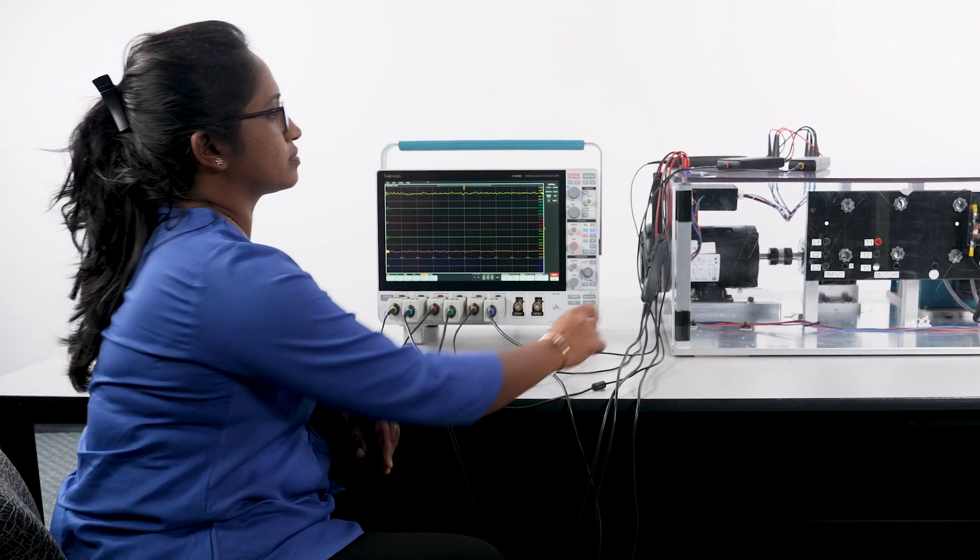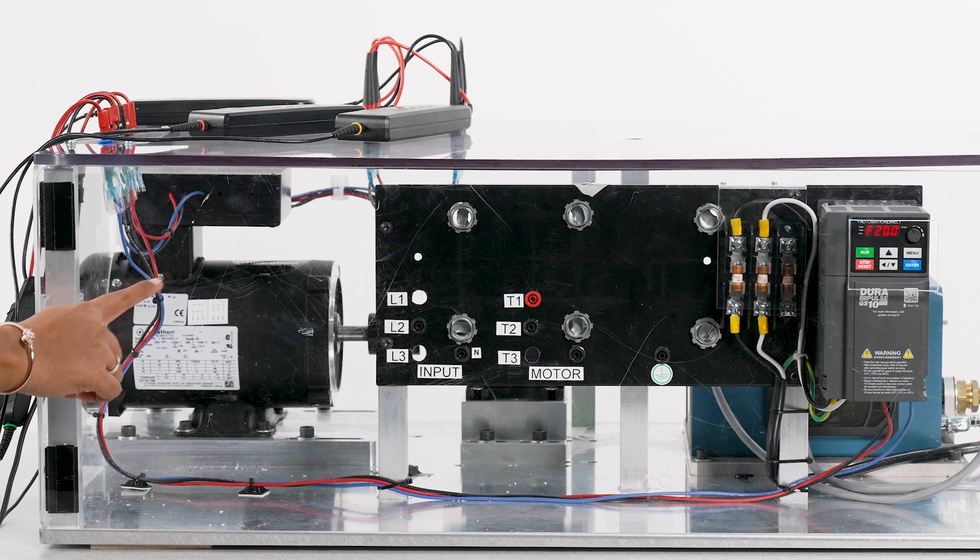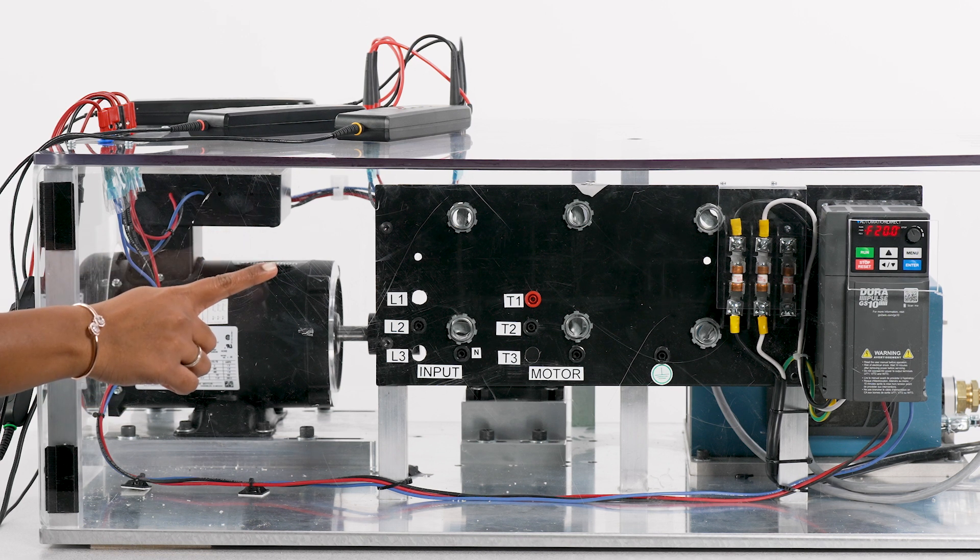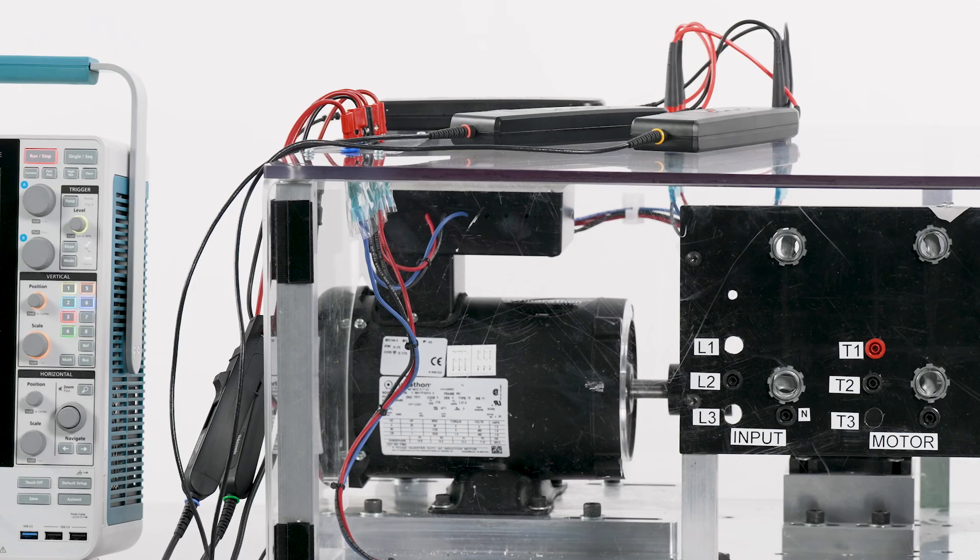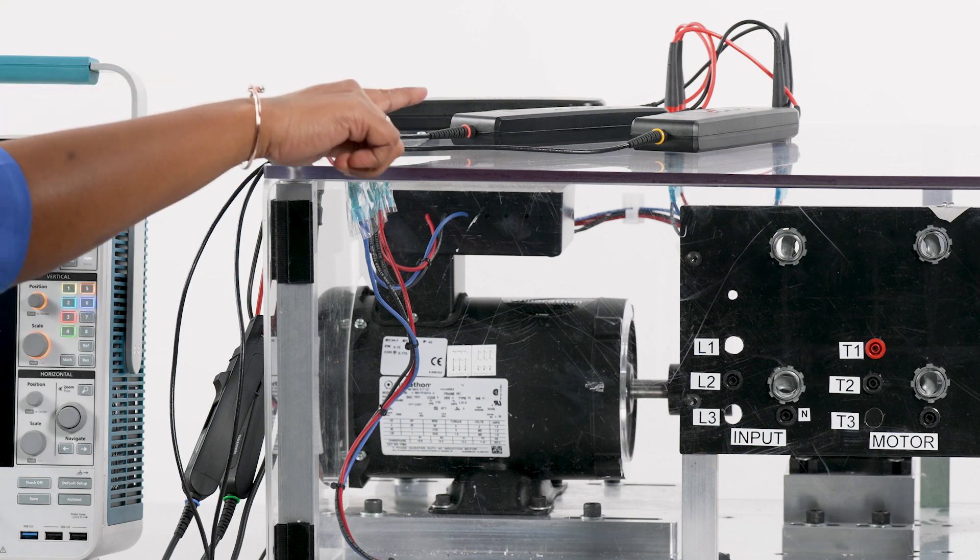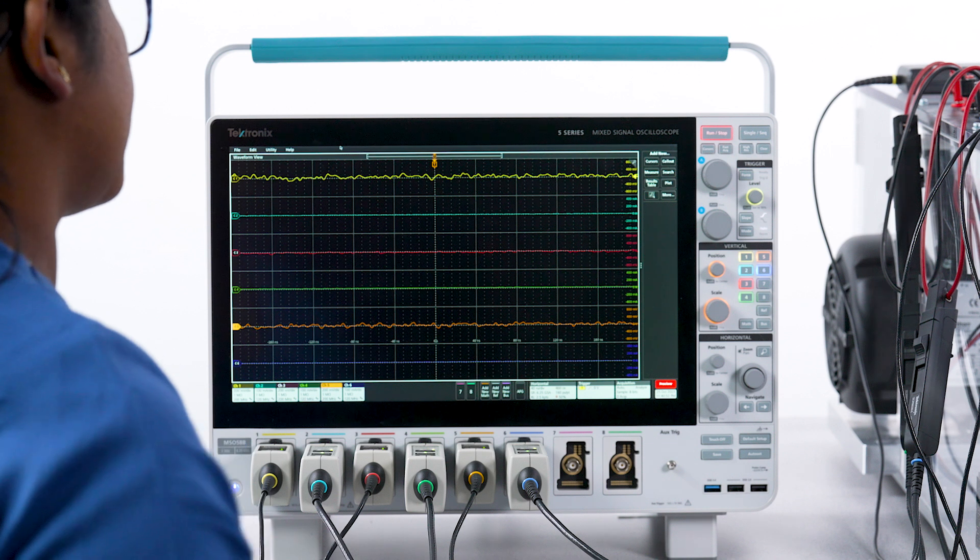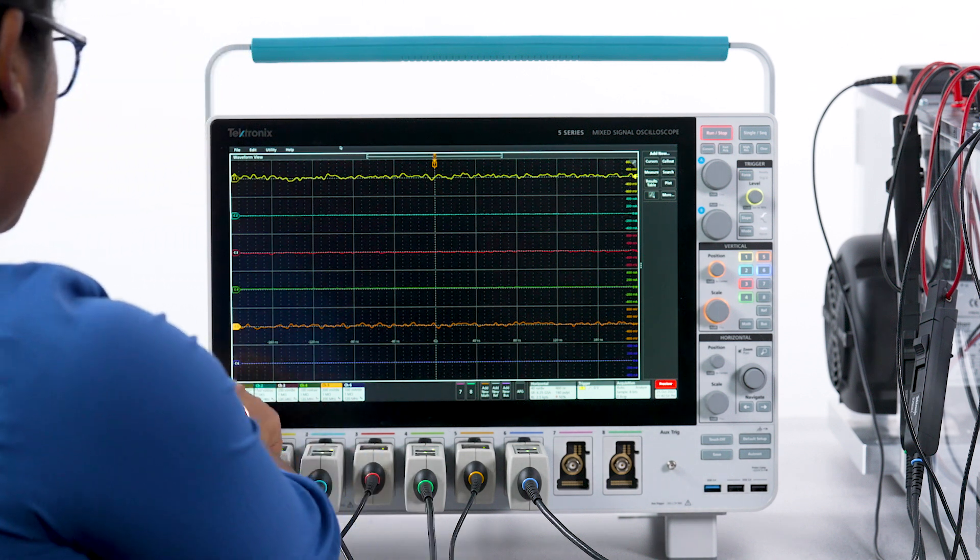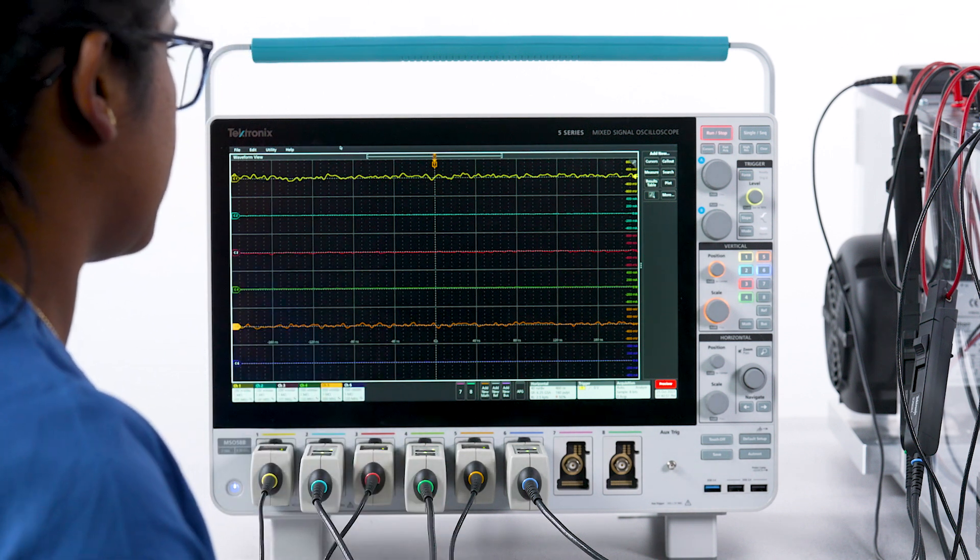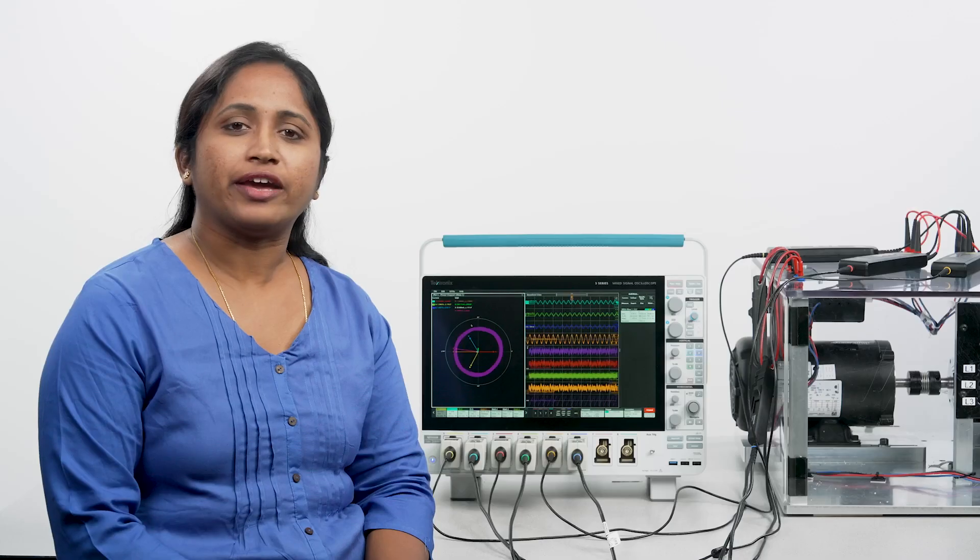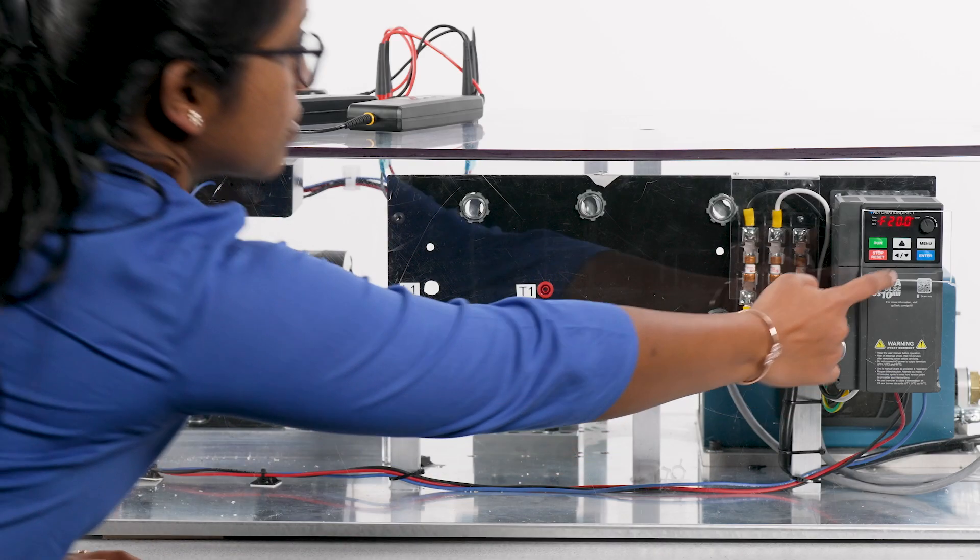I'll be using this small 1 horsepower induction motor with a variable frequency drive. The drive is powered by 120 volts single-phase AC power. The differential voltage probes are connected to channels 1, 3, and 5 of the scope. The current probes are connected to channels 2, 4, and 6. I have already deskewed the current and voltage probes to eliminate errors due to variations in probe delays. With everything connected and set up, I'll be starting the motor drive.